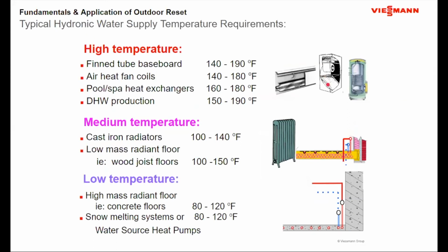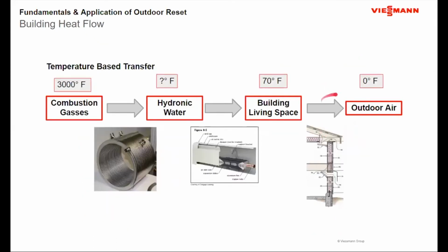we have now figured one of the pieces of the puzzle, the main component of designing that heating system. We know how much heat the building is losing under design conditions. So we know how much heat has to be put into the building space, and we know how much heat has to be put into the hydronic water. So now we've kind of hit a balance point all the way across. Now, the one thing that we haven't touched on yet, though, is really the hydronic water temperature. So I've got to set that hydronic water temperature.